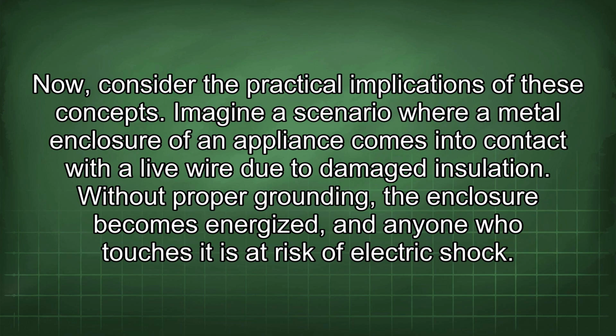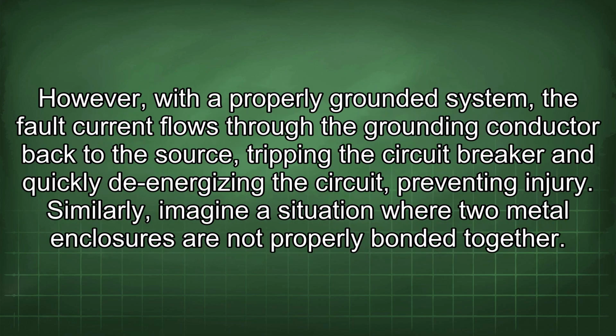Now, consider the practical implications of these concepts. Imagine a scenario where a metal enclosure of an appliance comes into contact with a live wire due to damaged insulation. Without proper grounding, the enclosure becomes energized, and anyone who touches it is at risk of electric shock. However, with a properly grounded system, the fault current flows through the grounding conductor back to the source, tripping the circuit breaker and quickly de-energizing the circuit, preventing injury.